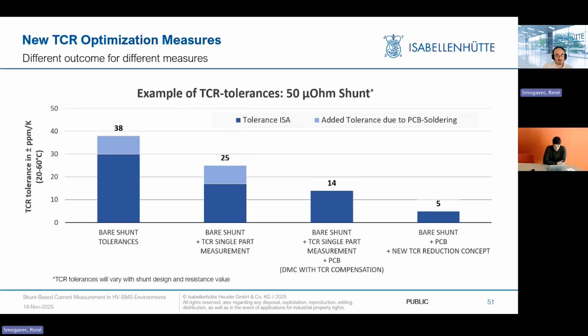So a 50 degrees Celsius temperature rise and a 50 microohm shunt tell, in turn, of a change of only 0.02% of the resistance value. So your ADC is going to detect it over high temperature changes, even though it sounds very insignificant, but in the shunt world, this value is very close to neutralization of the TCR, which is a big step in this technology.